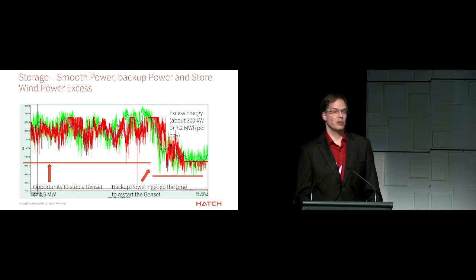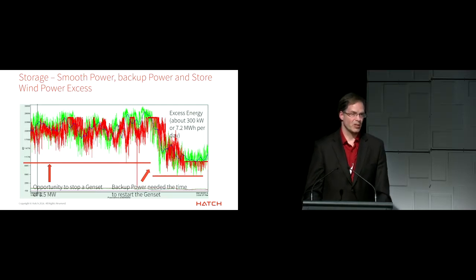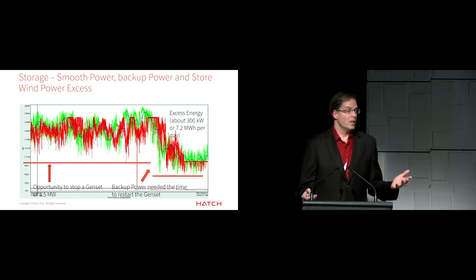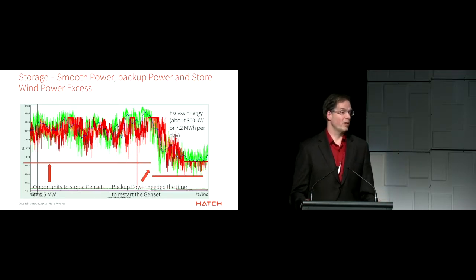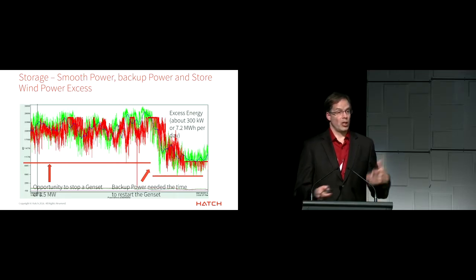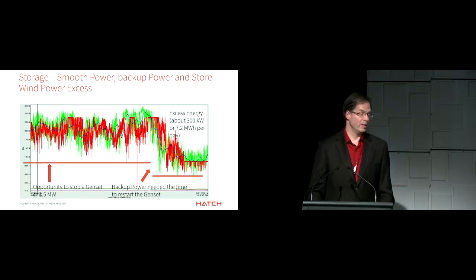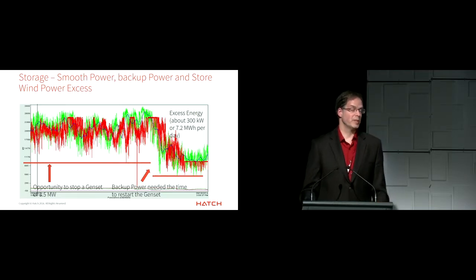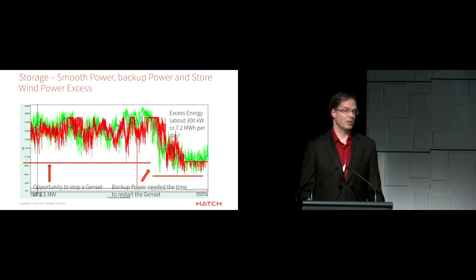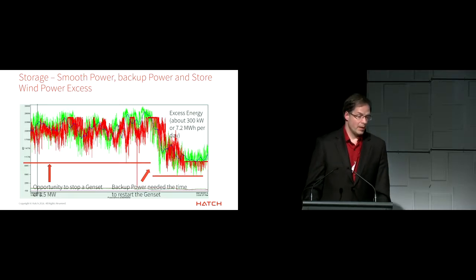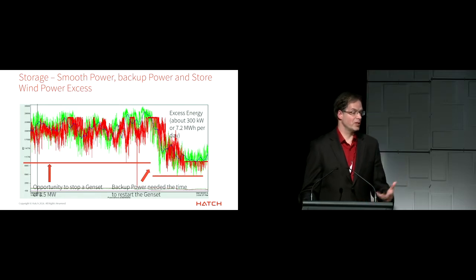Wind doesn't integrate well with energy storage at high penetration because it's not cyclical, it's not predictable. Your battery gets full, and the wind blows strong for 3 days, so you lose all that power. Solar, you charge during the day and discharge during the night, you have a cycle. At high penetration, solar beats wind, even though solar is more expensive in CapEx. With higher CapEx but higher penetration, you'll displace more diesel.